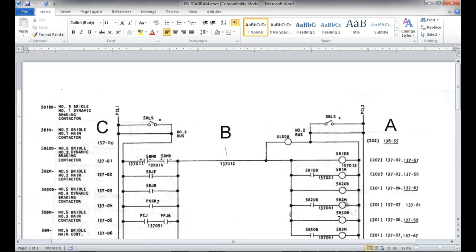So here's line 2 right here, and I'm looking for what? 5B1DB. Here's line 2, 5B1DB. There it is. Okay. Make sense? If it's underlined, it means that we would be looking for a normally closed contact. But we can't see it because it's in line 57, and we don't have line 57 on the drawing.